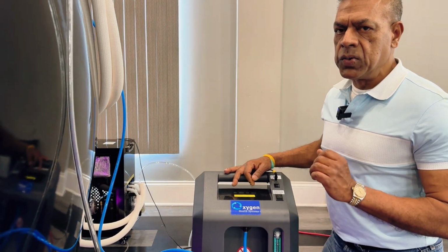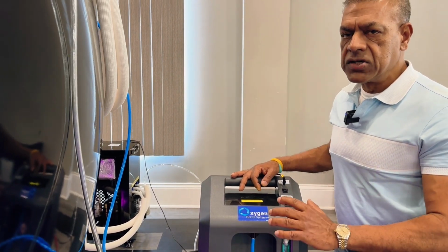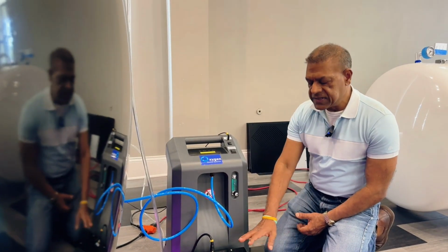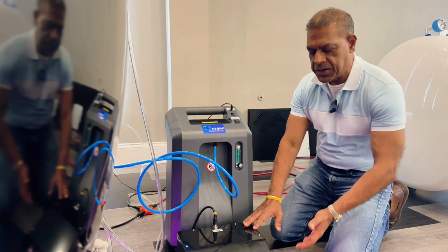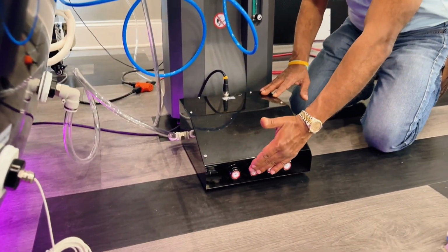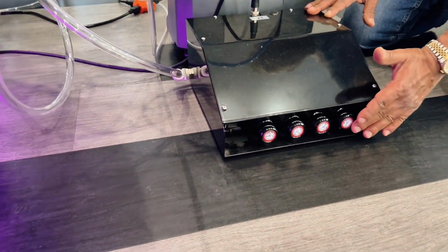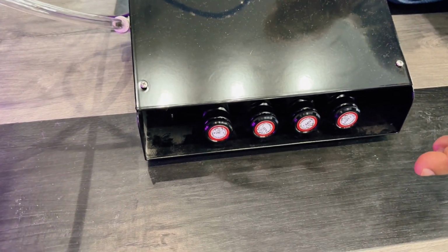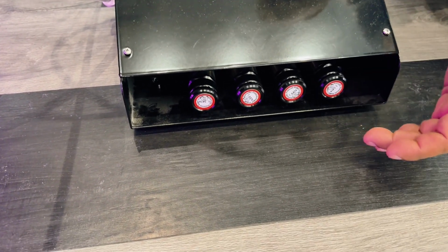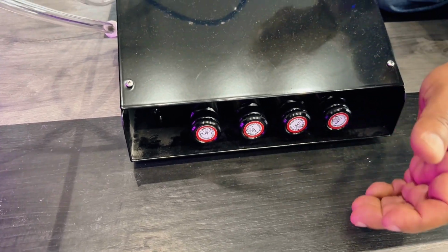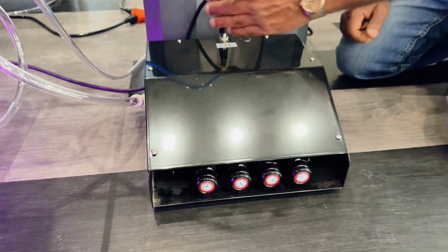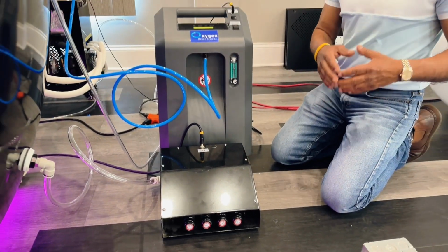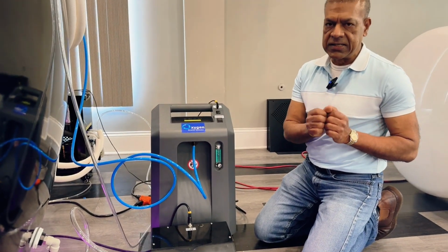Next, we will show you the progressive control unit that controls your variable pressure. Here is the progressive control unit, and here you have the 4 pressure release valves. These valves would depend on your model, which would represent the pressure selection. Here I have 2.0, 1.6, 1.6, and 1.3. It is connected via the interface that goes to the board and controls the user interface button selections that select a specific pressure.